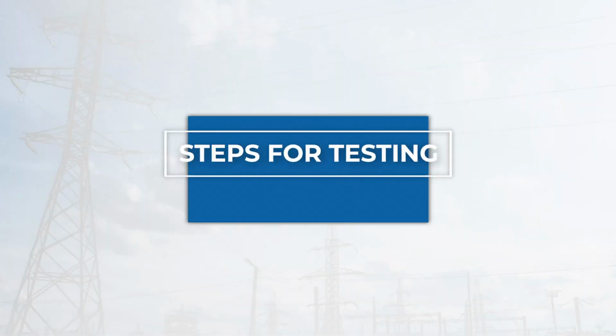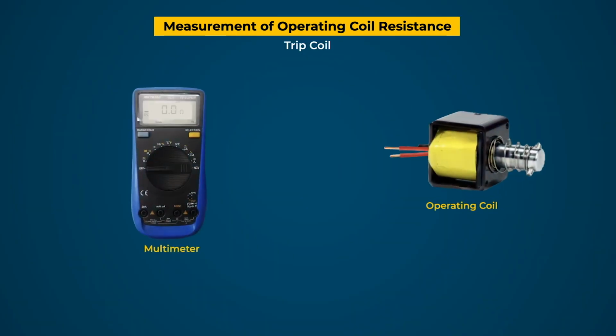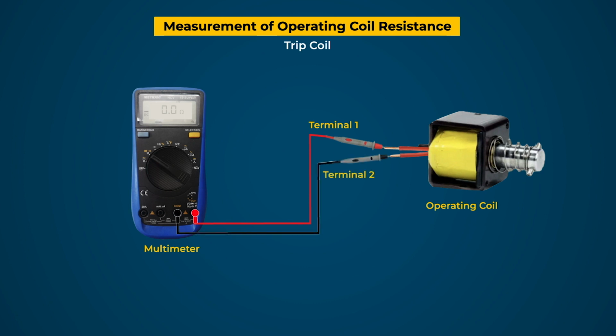Steps for testing. First, open the coil side connection of both terminals. Here we are measuring the resistance of the trip coil. Now select the ohm scale in the tester and connect the ohm terminal of the tester to one terminal of the coil and connect the common terminal of the tester to the other terminal of the coil.